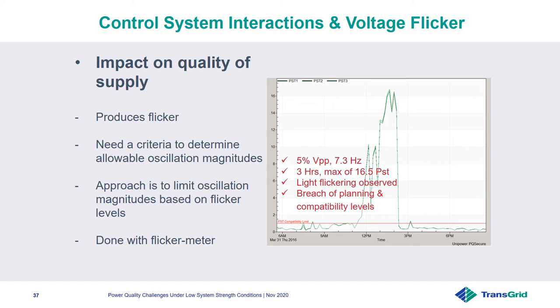planning and compatibility levels. So we concluded that small sustained oscillations like these are not acceptable and need a criteria to determine the allowable oscillation magnitudes. So the approach is to limit oscillation magnitudes based on the flicker level it produces.